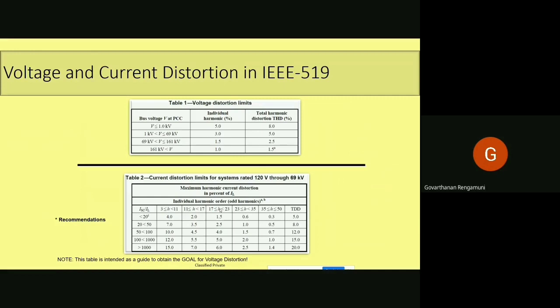This slide shows the voltage and current distortion limits prescribed in IEEE 519. The first table shows the voltage distortion limits at different bus voltages, what the individual harmonic limits should be, and what the total harmonic distortion should be. This is the main aim. Whatever you are doing, you have to maintain the voltage distortion limits at the PCC. To maintain the voltage distortion limit, the extent to which we can inject current distortion is prescribed in table 2.